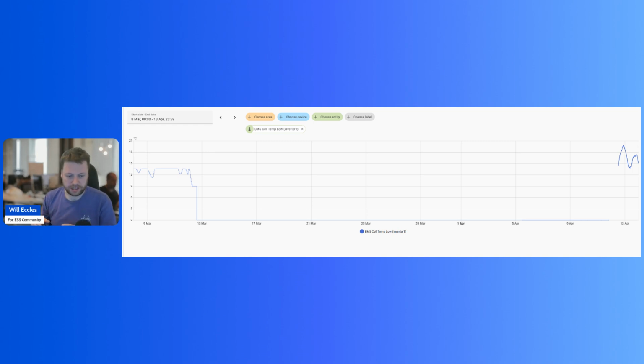Through process of elimination, I was able to prove that this battery is the one with the fault. Using any other combination of batteries, it works fine. But this battery, when in series in the stack, whether a stack of 2 or 7, would drag the whole system down.